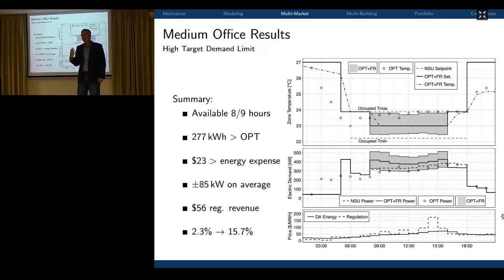So why do I consume more energy? You need to have a lower temperature set point to have that flexibility. Exactly. I need to have a lower temperature set point in order to be symmetrically able to go up and down. And the reason I can go up and down here is because I've taken away the 325 kW demand limit. I've taken off the lid. I allowed the building to do whatever it wants to do. So you can see economically I have significant savings, but it comes at an increase in energy consumption.